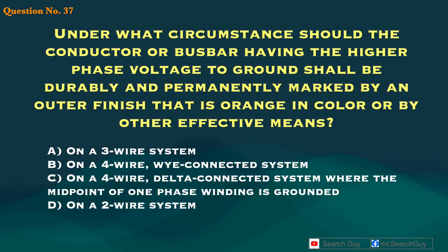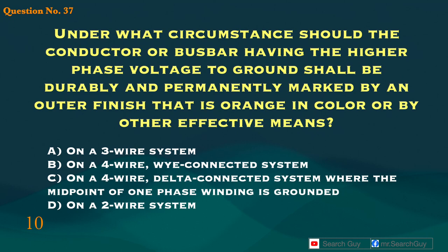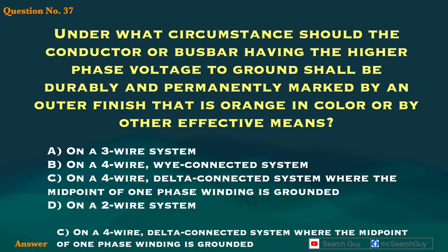Question 37. Under what circumstance should the conductor or bus bar having the higher phase voltage to ground be durably and permanently marked by an outer finish that is orange in color or by other effective means? A. On a 3-wire system. B. On a 4-wire Y-connected system. C. On a 4-wire delta-connected system where the midpoint of one phase winding is grounded. D. On a 2-wire system. Answer: C. On a 4-wire delta-connected system where the midpoint of one phase winding is grounded.